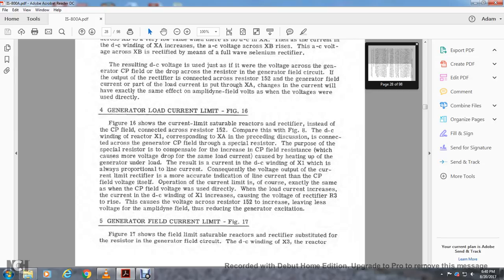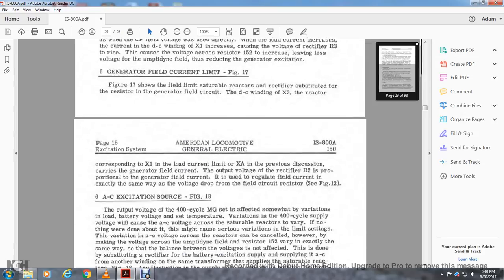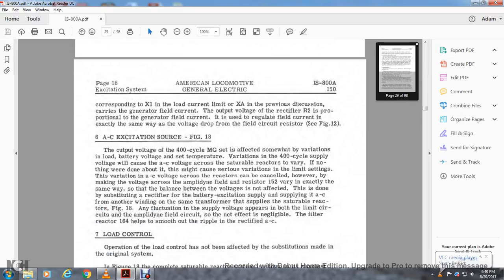Operating with the current limit: as load current increases, current in DC winding X1 reactor increases, causing the voltage from rectifier R3 to increase, causing the voltage drop of resistor 152 to increase and leaving less voltage for the amplidyne field, thus reducing the generator excitation. Generator field current limit, figures 16 and 17: figure 17 shows the field limit saturable reactor with rectifier substituted for the resistor generator field current circuit. The DC winding of reactor X3 corresponds to X1 for load current and XA in the previous discussion. The output voltage of rectifier R2 provides generator field current control in exactly the same way as the voltage drop of the field resistor.